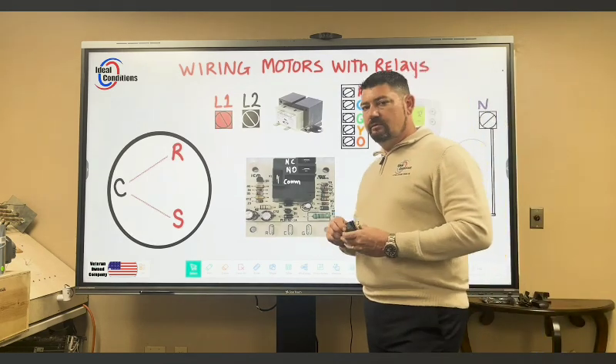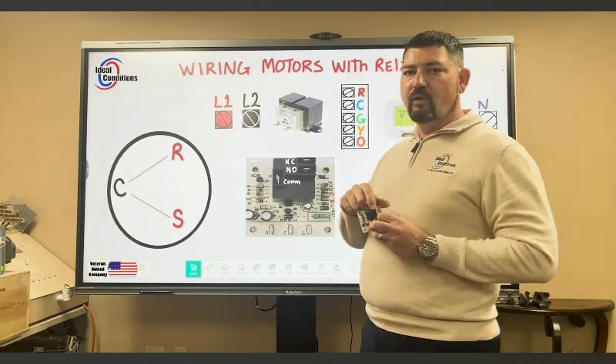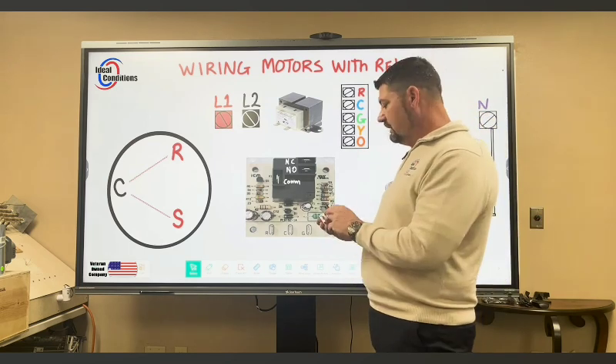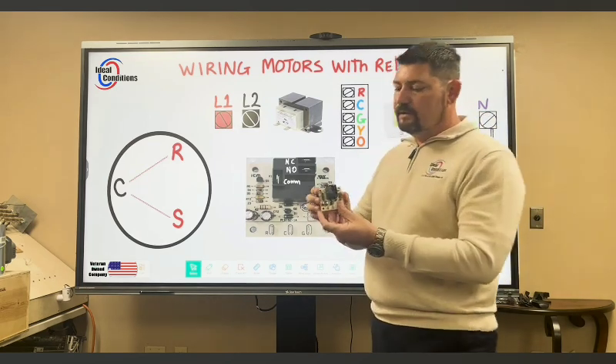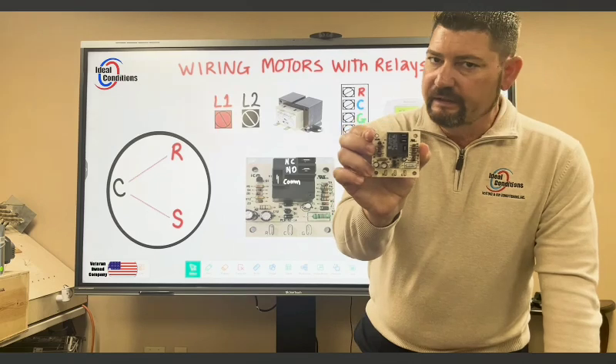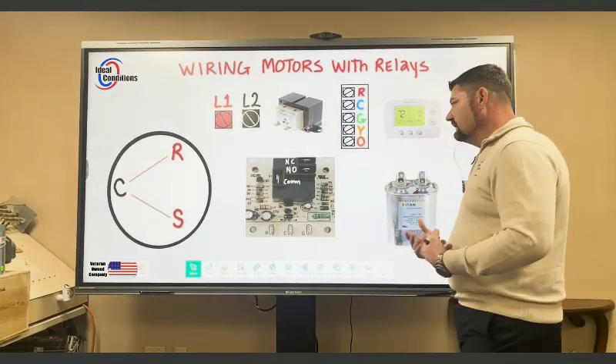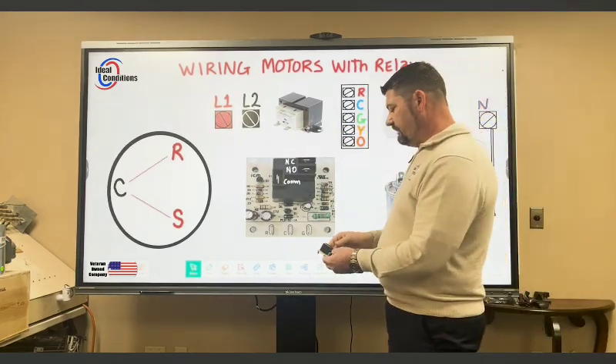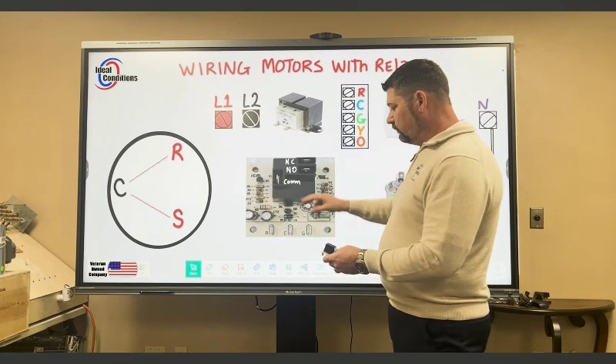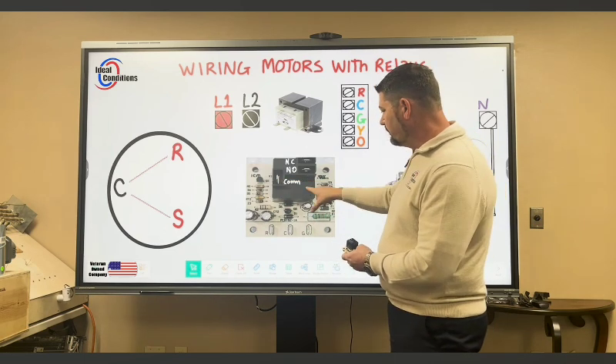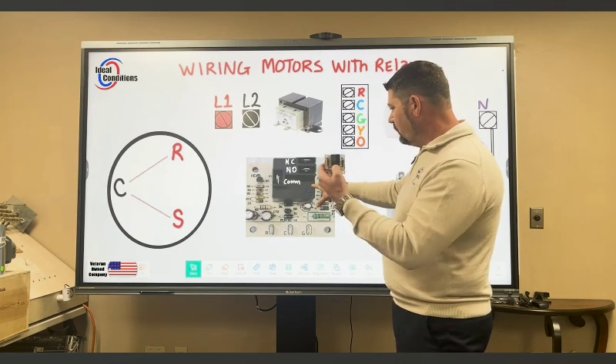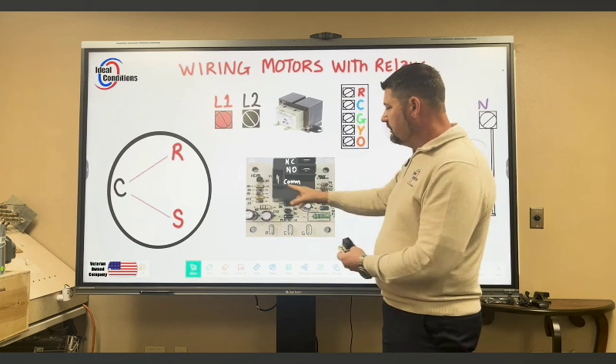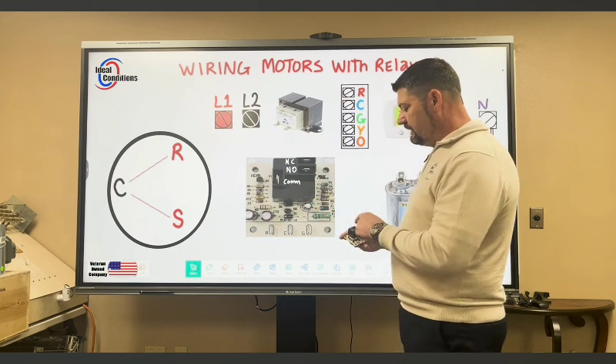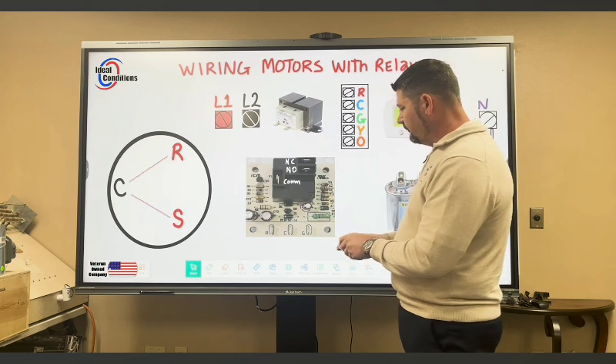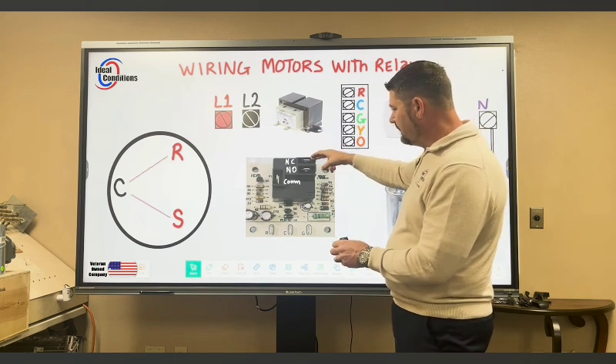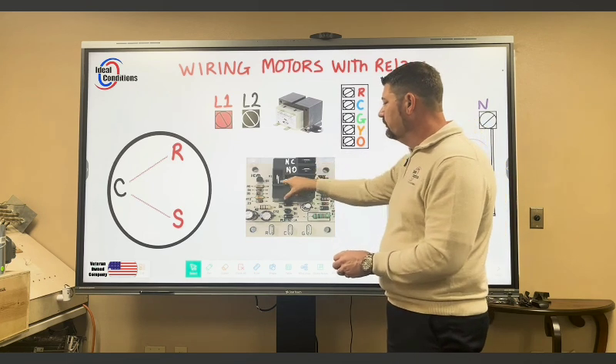Took the liberty to notate which one is common and normally open, normally closed. If you look at the one that I have here, it looks a little bit different depending on the manufacturer. It's not a big deal. Both of these are actually made by ICM. This one has my common terminal over here that I'm holding in my hand. On this image, the common terminal is over to the left, but pretty much the normally closed portion is always going to be on the top side, and the normally open will always be in the middle, closest to the common.